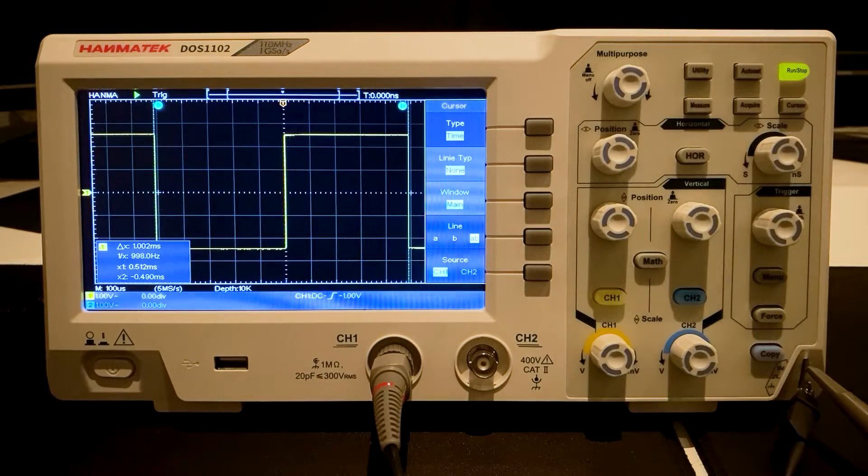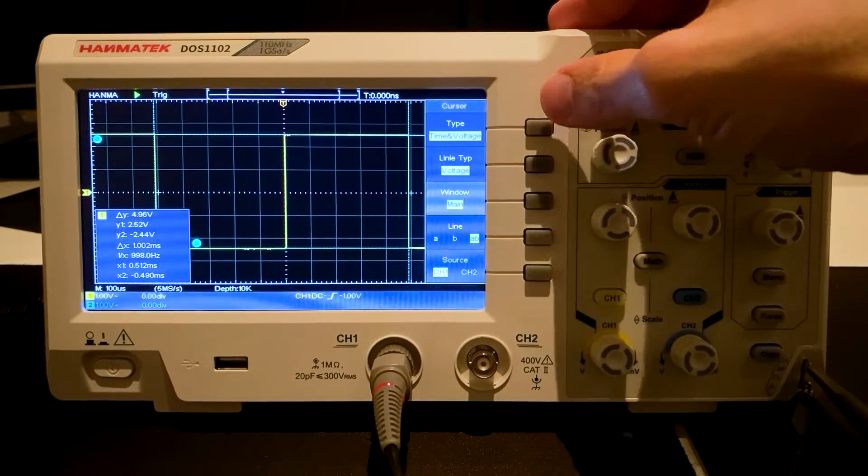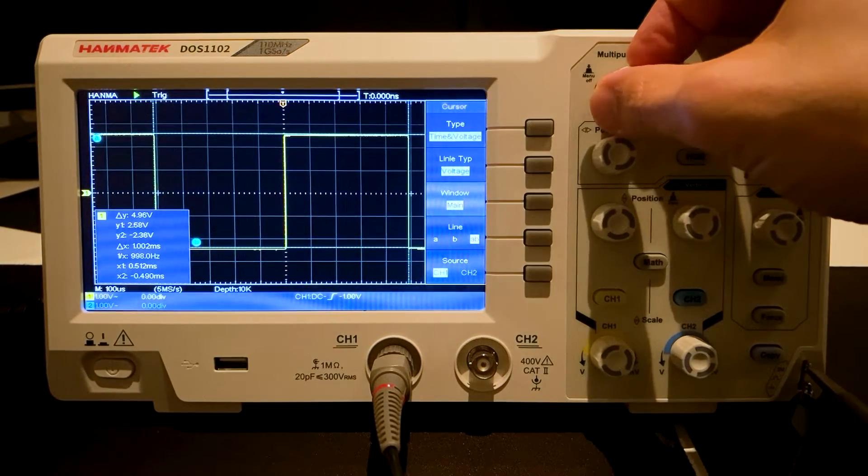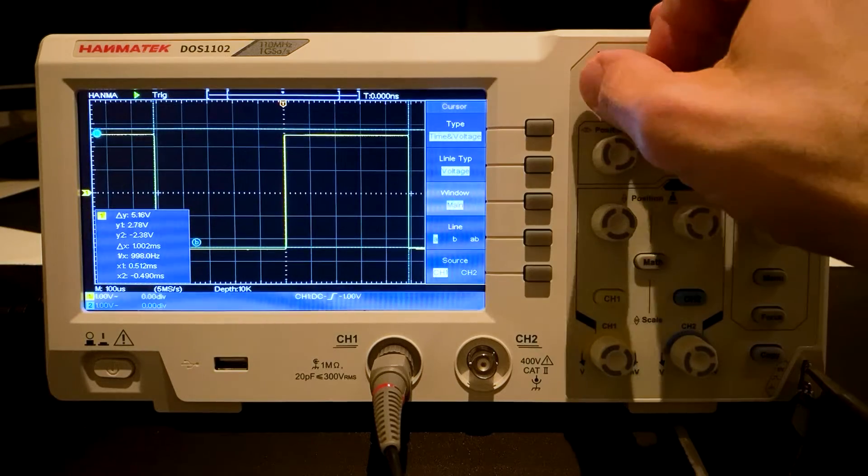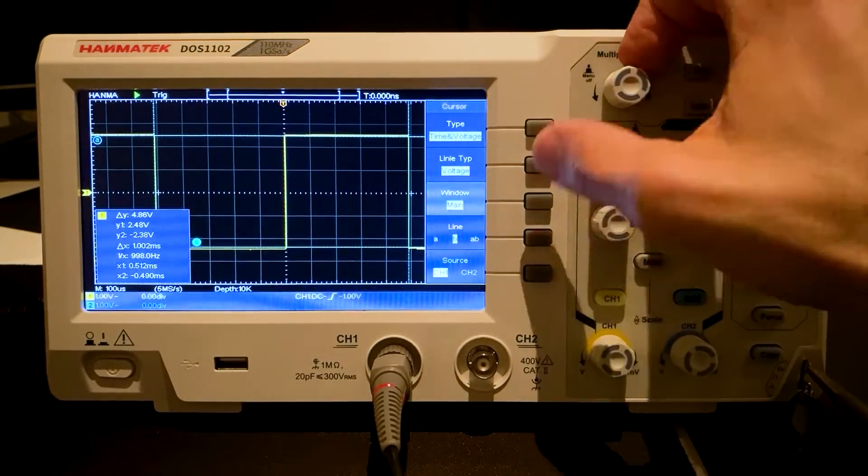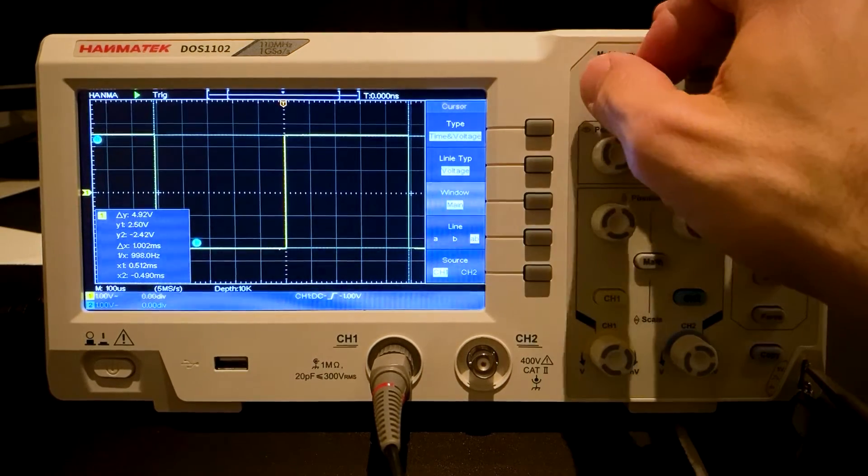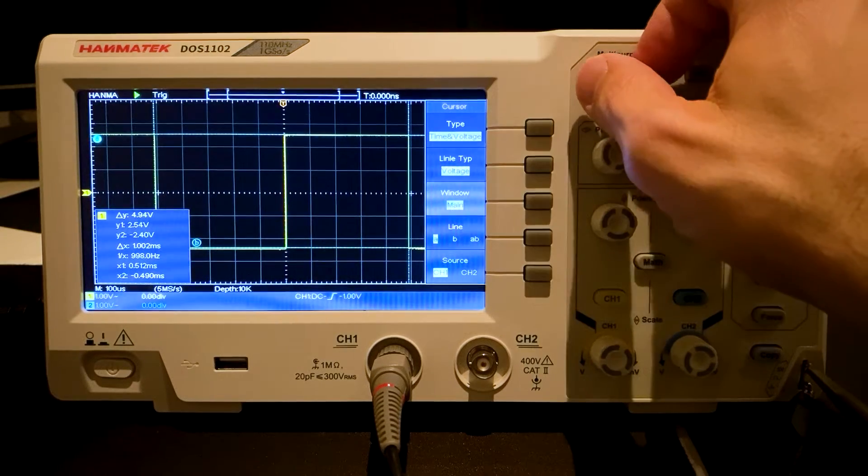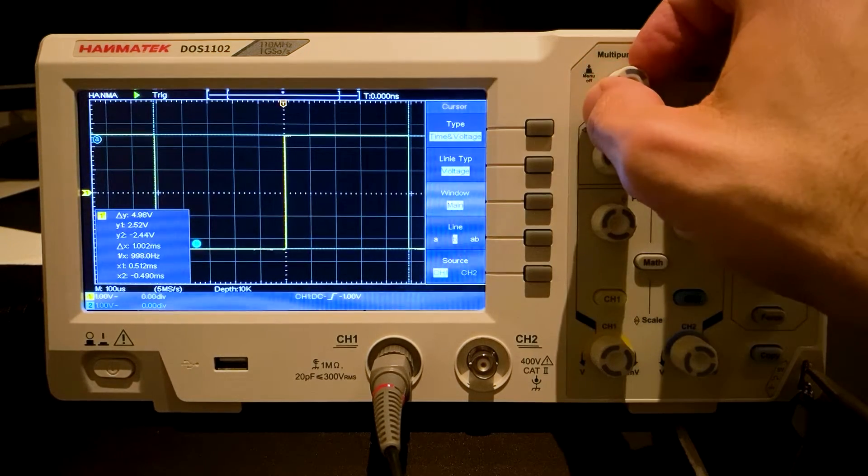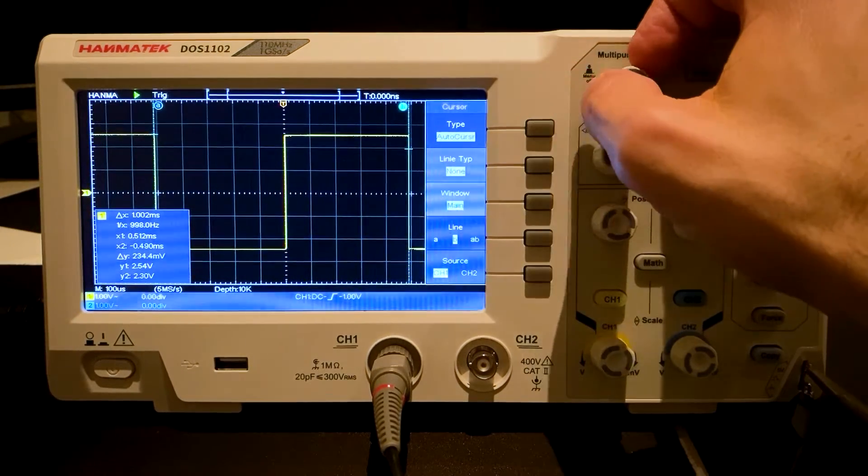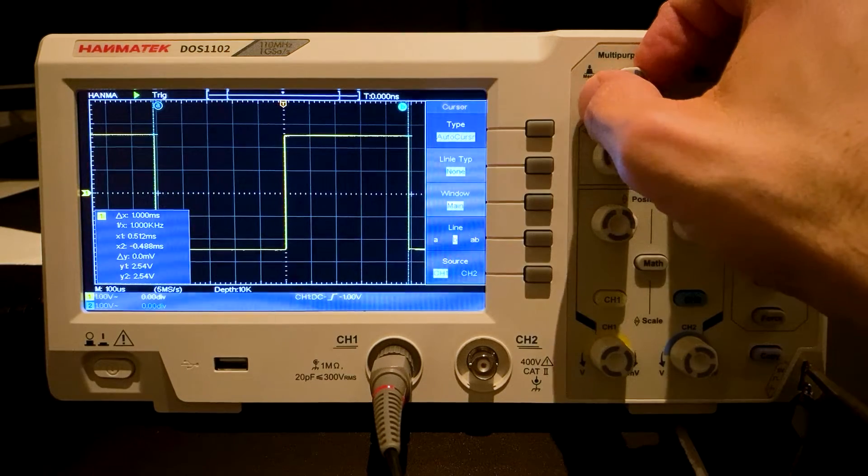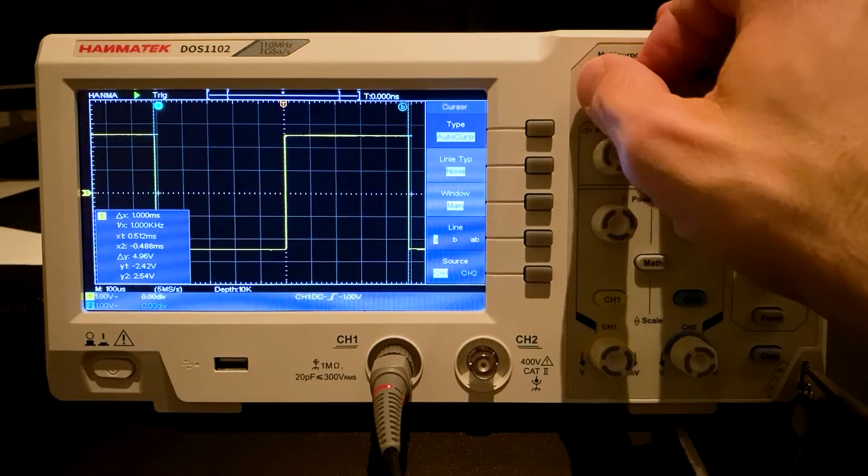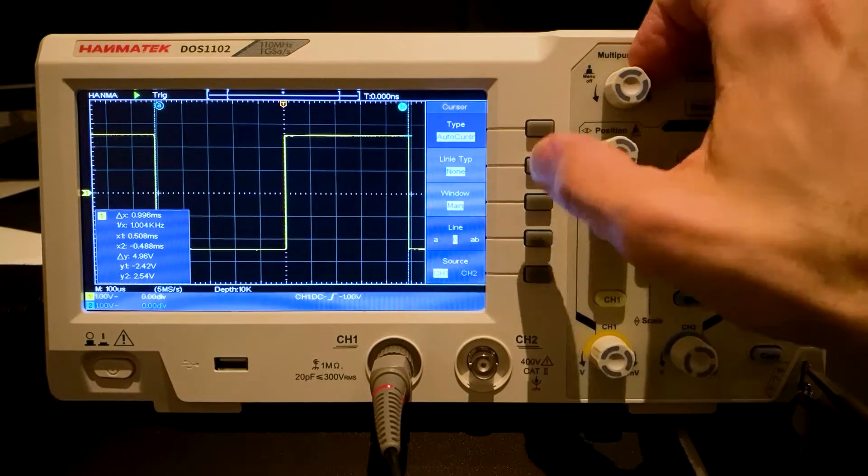In the Time and Voltage type mode, four line pairs for Time and Voltage can be positioned simultaneously. The AutoCursor mode is similar to Time Voltage. In contrast, the oscilloscope chooses which value is measured first. Of course, a measurement can only be carried out if a probe is connected.